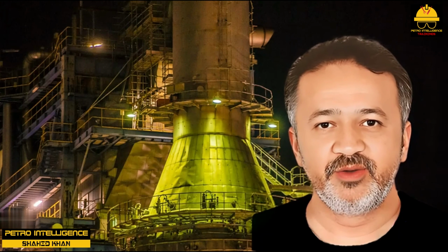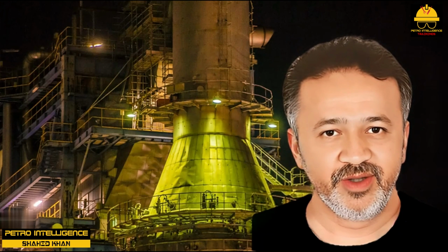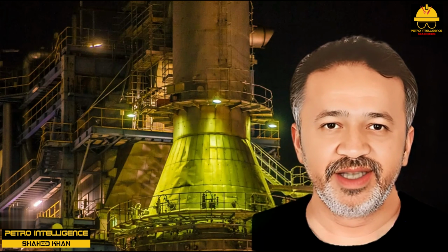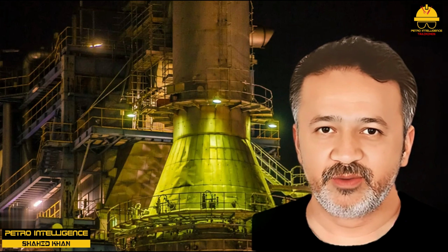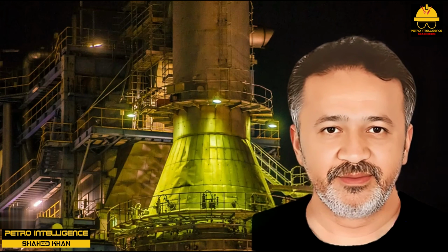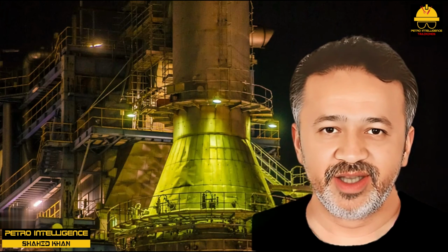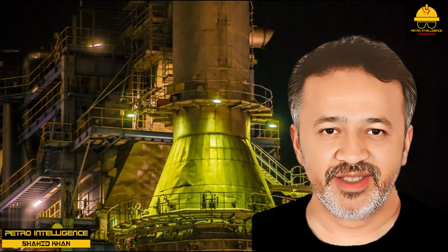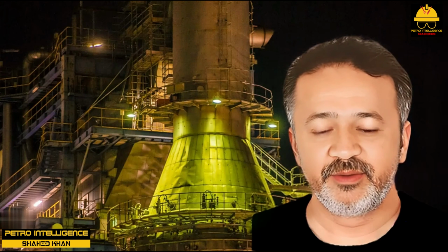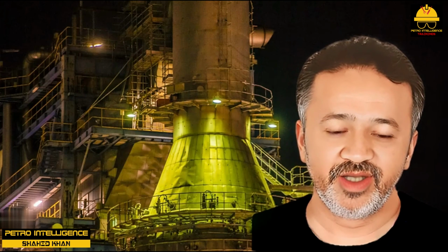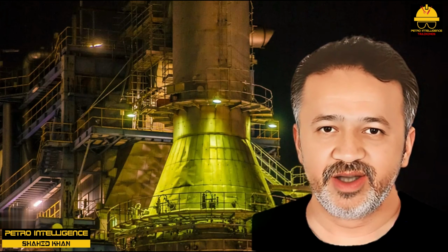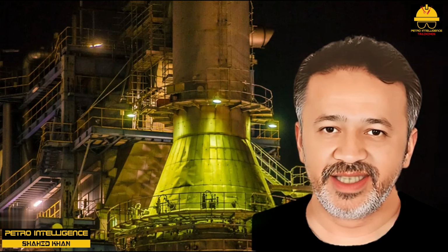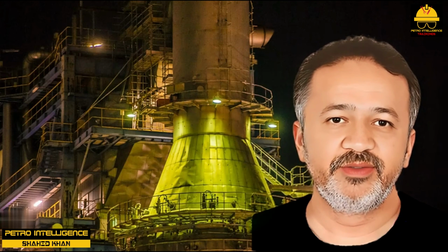Lack of air affects draft and combustion. Normally, opening the air registers at the base of a heater reduces draft, that is, increases pressure below the bottom row of convective tubes. This happens because the extra combustion air creates more flue gas, which results in an increased delta P across the convective section tubes and the stack damper. However, if the heater is operating in an oxygen-deficient environment, or it is running below the point of complete combustion, draft will likely increase as the air registers are opened.